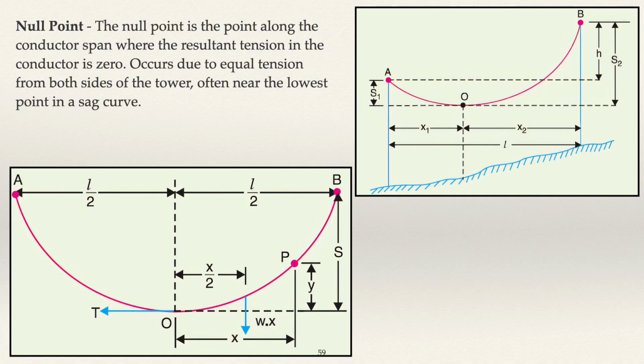Null point. The null point is the point along the conductor span where the resultant tension in the conductor is zero. Occurs due to equal tension from both sides of the tower, often near the lowest point in a sag curve.